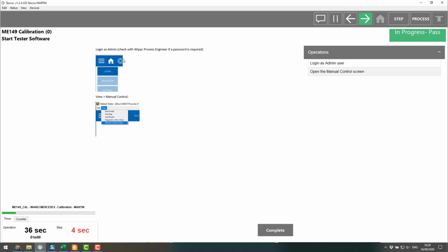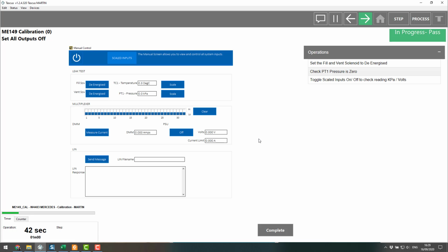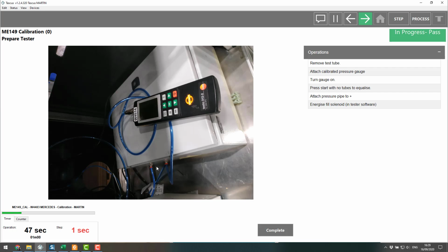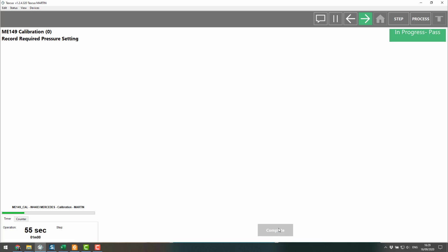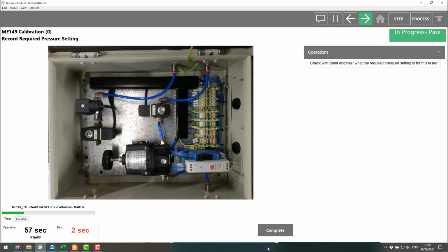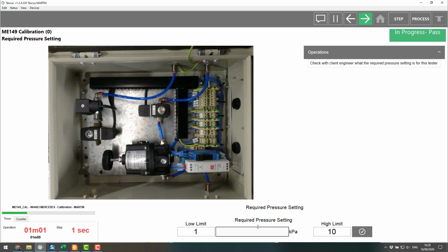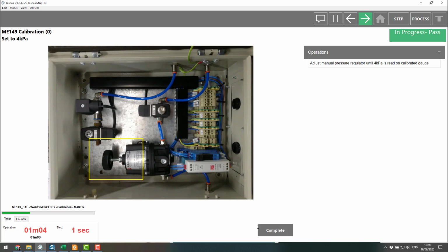And now it's telling me what menus to navigate in the software to open up the control screens. I've done that. I'm going to de-energize the system and then I'm going to make the physical connections with the calibration equipment. And then it's going to ask me to check what the pressure setting is. So that's the first data that I will record. So that's at 6 kilopascals. And now it wants me to start running through the calibration process.